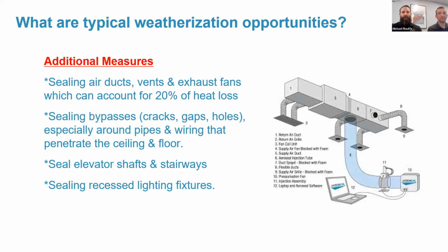And there's also additional opportunities in terms of either semi-conditioned or intentionally conditioned stairways and sealing unconditioned areas such as elevator shafts and areas above recessed lighting fixtures. Those are all areas where conditioned air tends to find its way in, even though it's absolutely not needed.